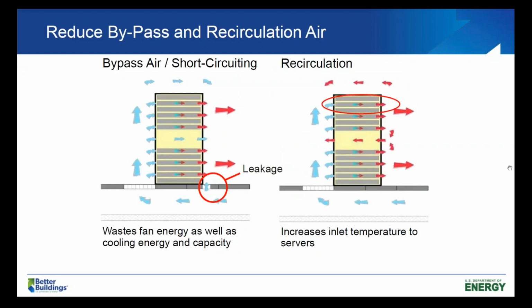All right, but in reality, we have two problems. We have bypass, which is cool air that goes back to the cooling equipment without having run through the IT equipment. And then we have recirculation, which is hot air going back through the IT equipment without having been cooled by the cooling equipment. And you can have bypass and recirculation at the same time. Most data centers do have that to a certain extent. You can have it external to the rack as shown, and you can also have it internal to the rack. Both are bad. The recirculation is worse in terms of IT equipment getting air that's warmer than it should. Next slide, please.